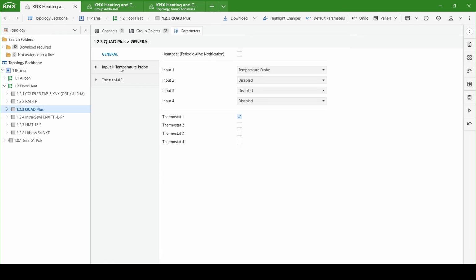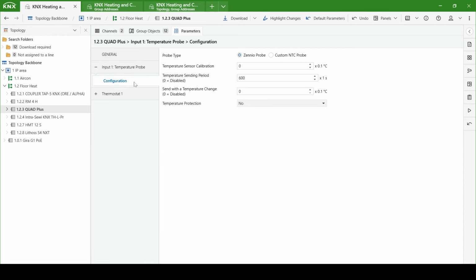Looking at the parameters, we have the ability for 4 different probes to come into the device. Those probes are not automatically connected to the thermostat, and you'll see why this is important soon. We also have the ability for 4 thermostat logics to reside on this device, and they can take their temperatures from different places — they don't have to take it from the Zennio probes or the temperature probes coming into that device. For this case, we're just going to use a Zennio probe, but we could use a customized or different type of NTC probe.